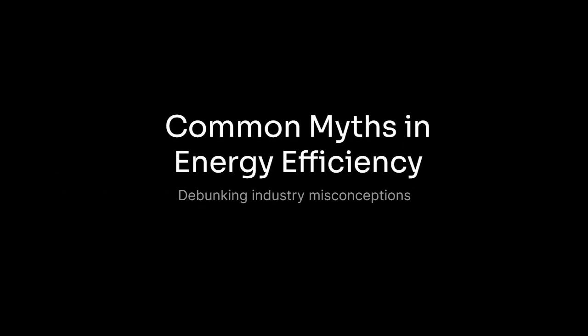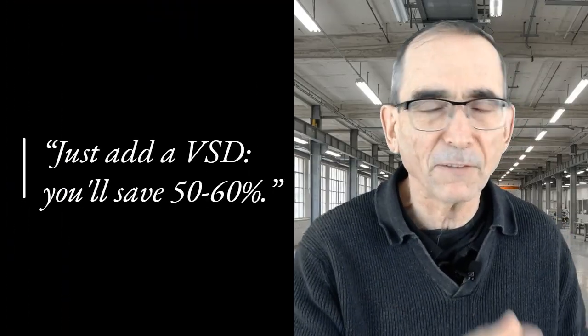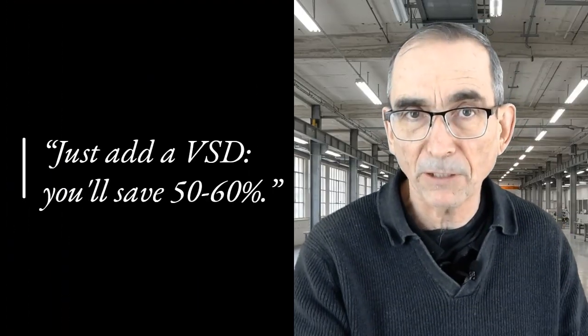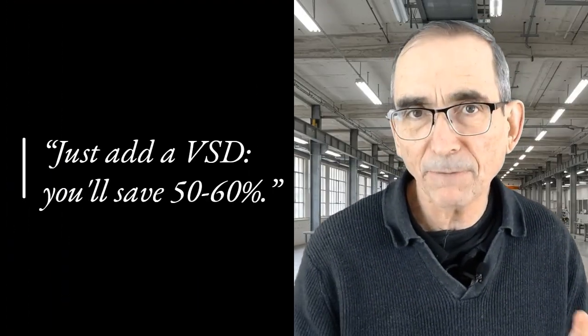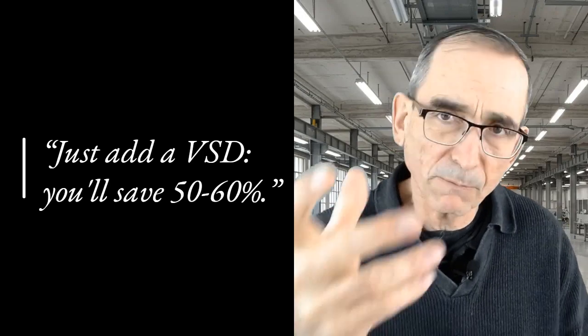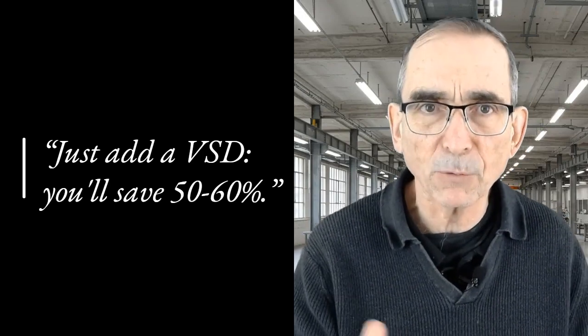So what are some of the myths that waste your time around industrial energy efficiency? And I want to talk about four things. Maybe you've heard of these, maybe you haven't. And possibly they're a little bit too simplistic, but a vendor may say, just put a VSD, a variable speed drive, or variable frequency drive, VFD, in this and you're going to save 50 to 60% on your energy use just by cutting the speed by 10, 15, 20%.